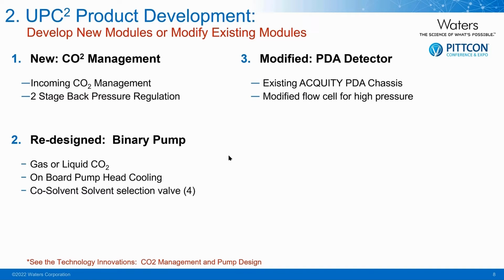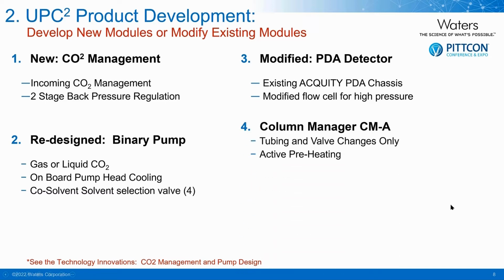In the column manager, we only had to do tubing and valve changes to allow for higher flow rates, as well as active pre-heating.